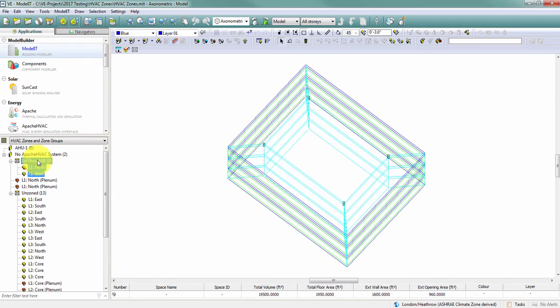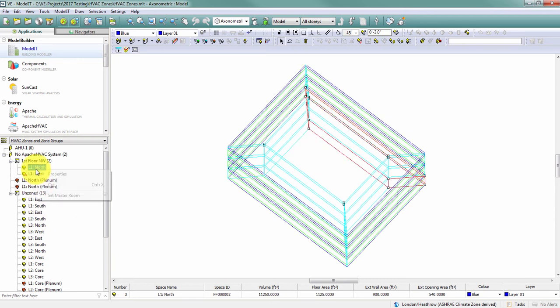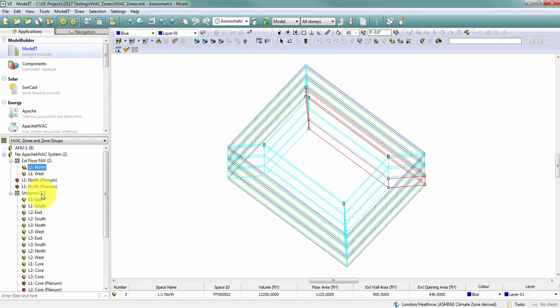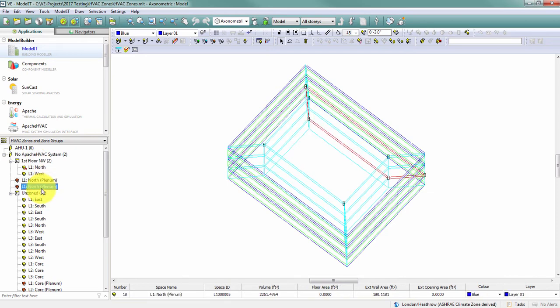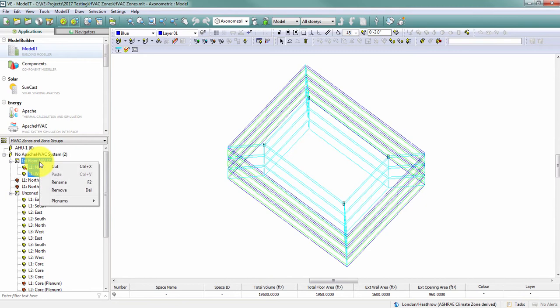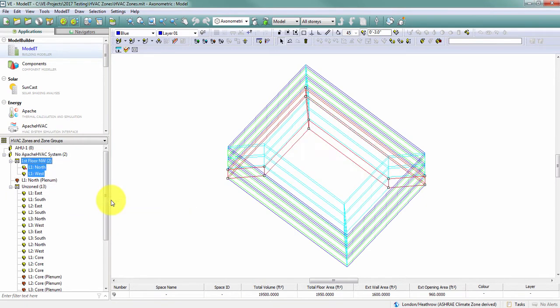I can change where my thermostat is located within this zone by selecting the space and right clicking on it to set it as the master room. Whichever space is the master room is the room that contains the thermostat. The way my geometry is built currently, each of these spaces has their own return air plenum. Since I can't have multiple return air plenums in a single zone, I have the option to right click on this zone, and in the plenums menu I can combine those return air plenums.